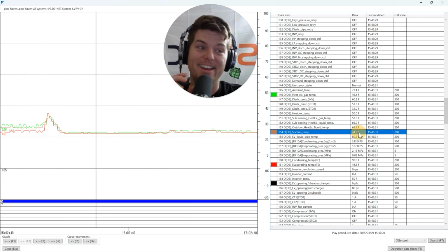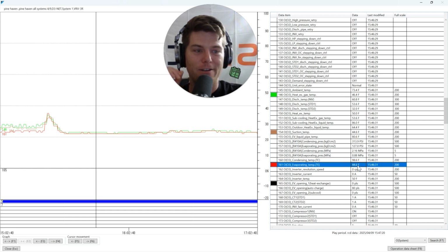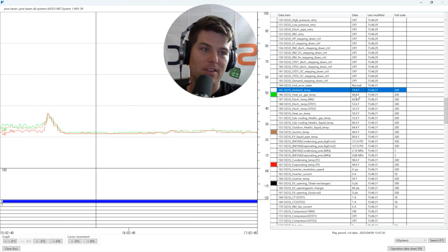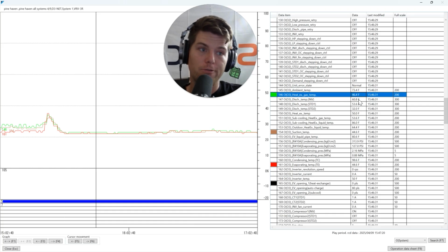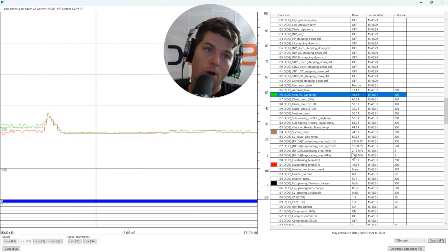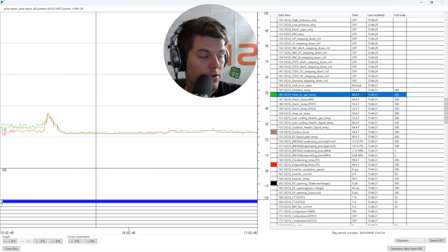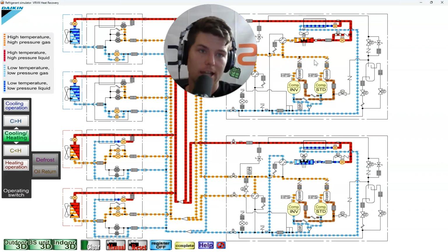That's not a good thing. 44.6 and 44.6. This tells me that not only is it not matching ambient like it should at 0 pulses, but the liquid refrigerant is flowing through this outdoor heat exchanger, dumping into the suction line, coming down the common suction line and back over to the other modules and creating liquid compression.